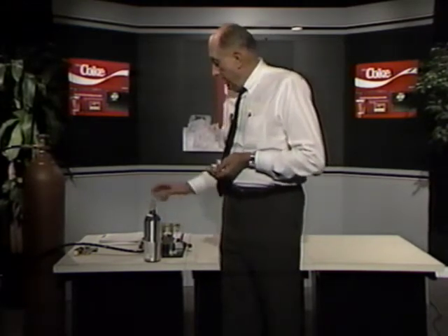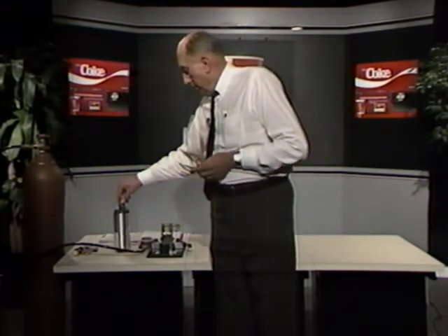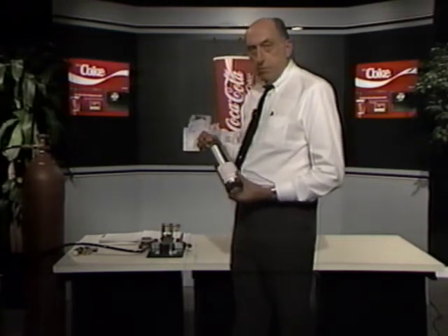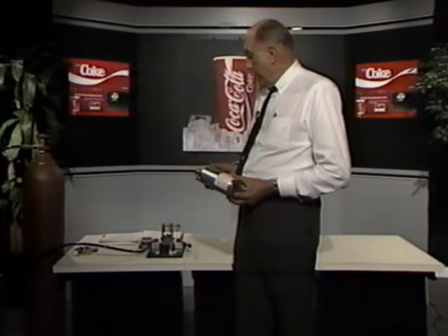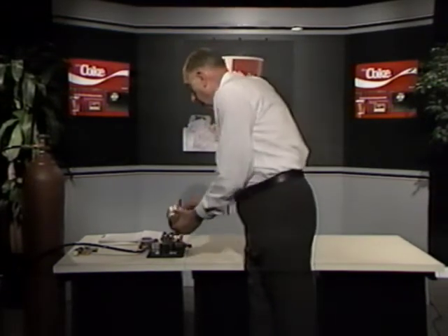The large cylinder holds 50 pounds of gas, and that gas is in a liquid form in the cylinder. We're transferring liquid gas. It's not gas in gaseous form. So the flow through the hose into the filling head is liquid CO2. I'm going to go through the procedure of putting a cylinder in the filling head and operating it just as if we were going to fill it.